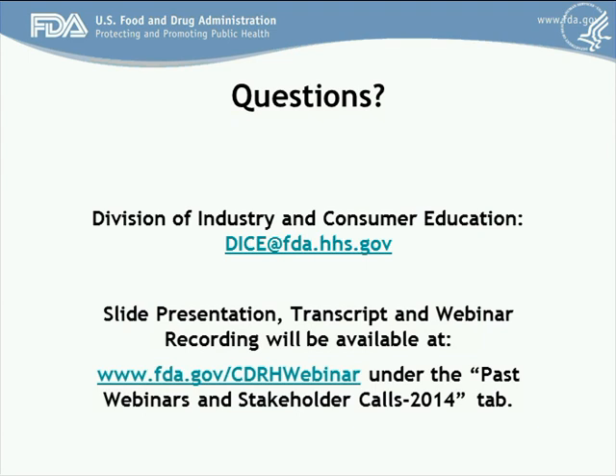And this is Linda Ritchie. I'm also from the Office of Device Evaluation. Can you repeat the second half of your question, please? Basically, if we could adopt the ISO 14971 risk management in lieu of using an IT network-specific standard on risk management. Certainly, the ISO 14971 standard is an FDA-recognized standard for risk management, and you are certainly welcome to use that as part of your risk management process. It's also important to understand that the risks that you might be trying to identify with regards to cybersecurity might also be well characterized by other standards that deal more with IT security. And so if you wanted to use a combination of the two, that would certainly be an option that we would be open to. Thank you.